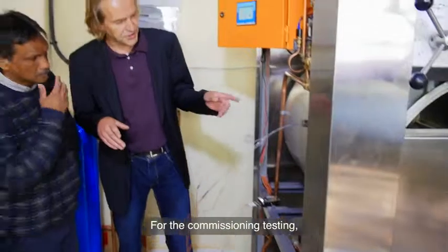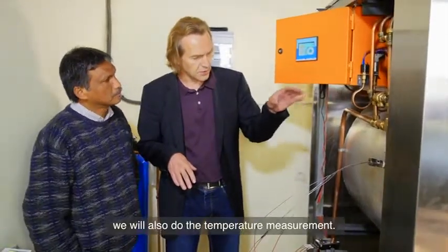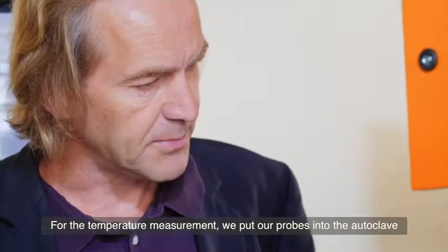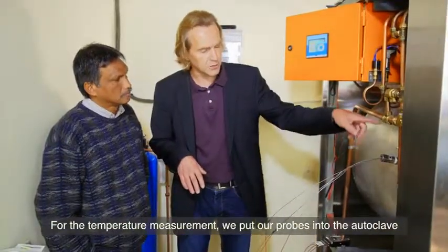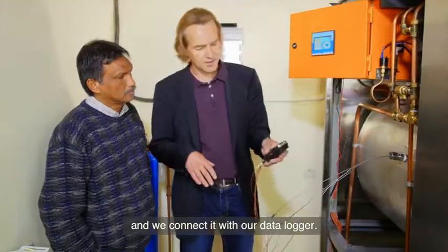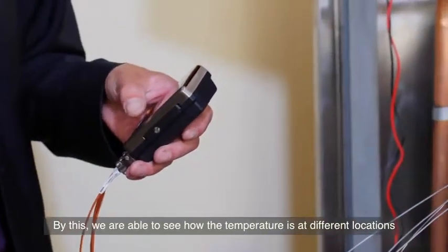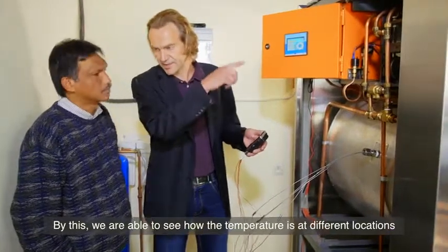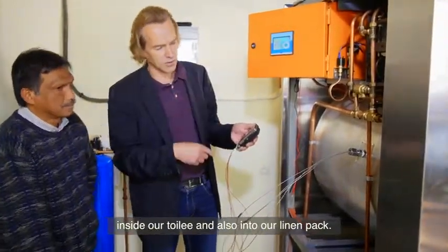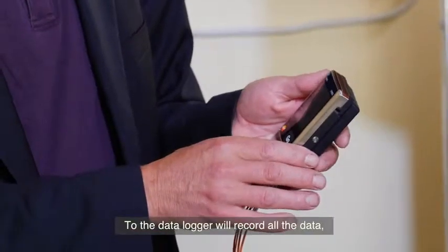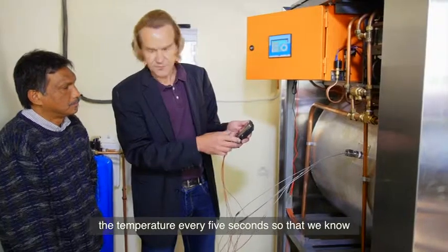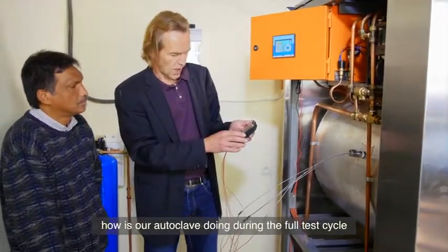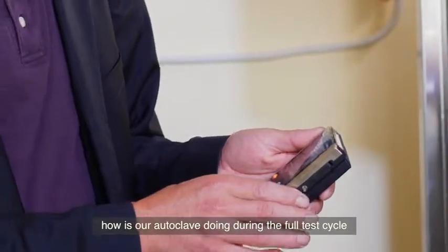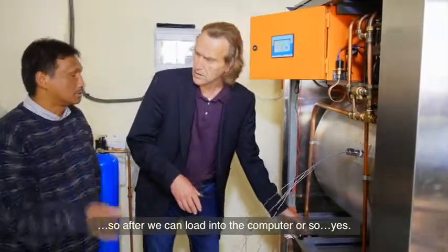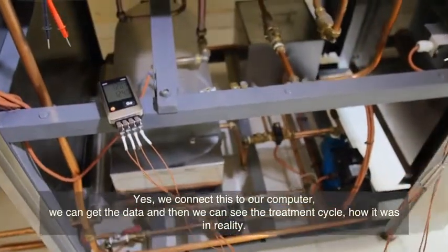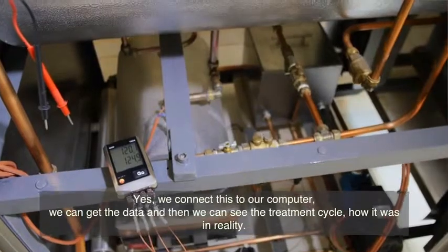For the commissioning testing, we will also do the temperature measurement. For the temperature measurement, we put our probes into the autoclave and we connect it with our data logger. And by this, we are able to see how the temperature is at different locations inside our trolley and also into our linen pack. So the data logger will record the temperature every 5 seconds, so that we know how is our autoclave doing during the process cycle. So after we can load it to the computer also. Yes, we connect this to our computer, we can get the data, and then we can see the treatment cycle, how it was in reality.